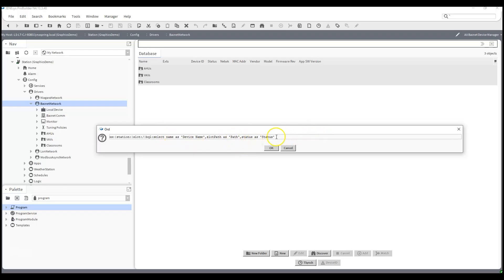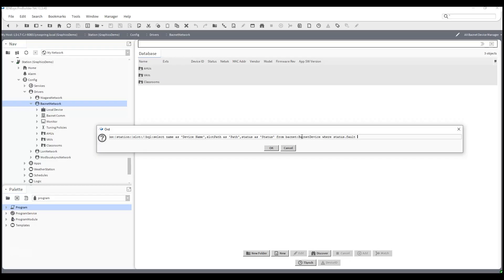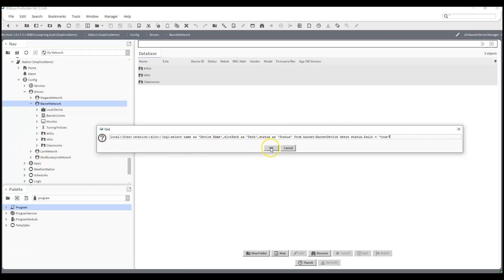Now we have the SELECT predicate. For the extent — where we're actually looking for things — I'll say FROM bacnet:BacnetDevice. Then WHERE status.fault equals true. So this is the complete query. Let's click OK and see the results.